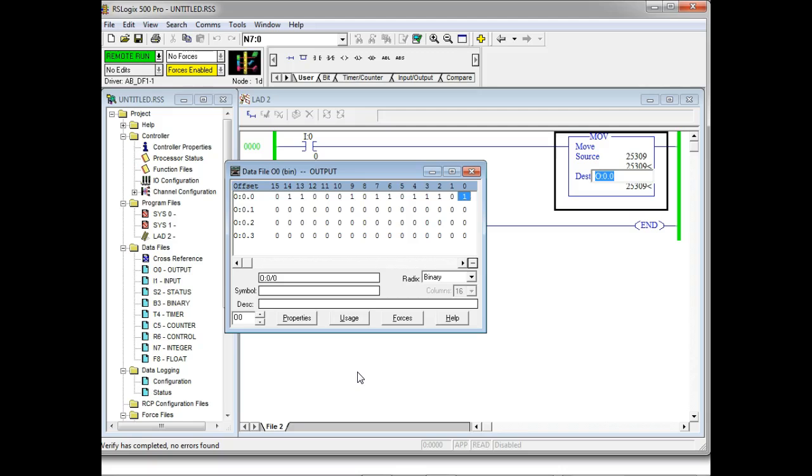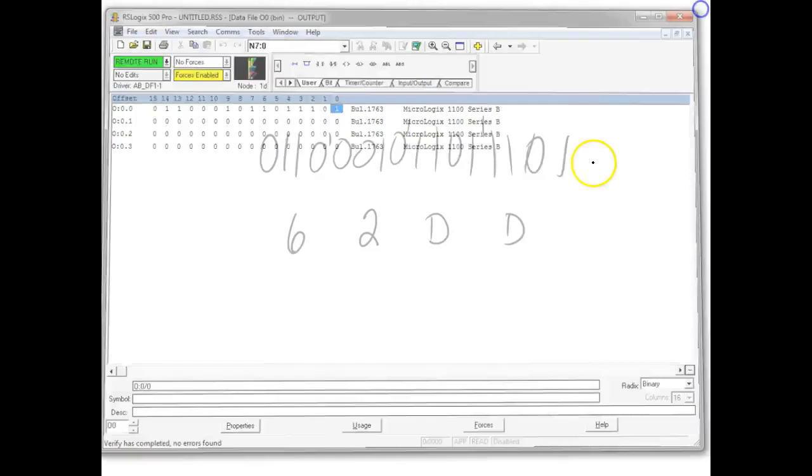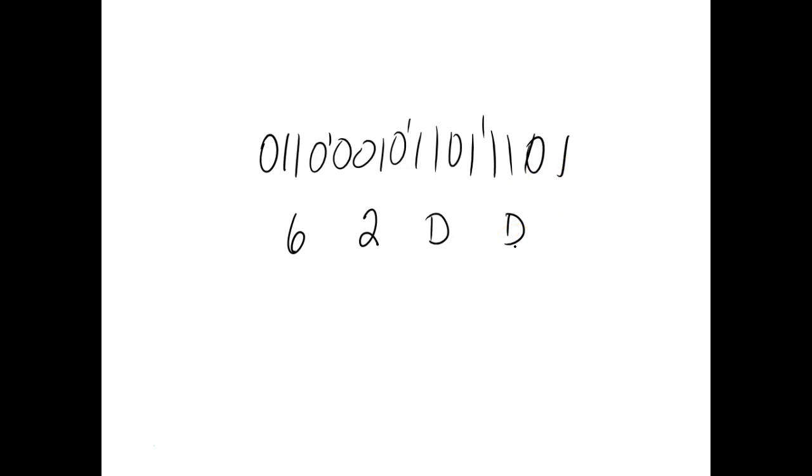So that's where these bases come into play, especially when we're dealing with getting information and sending it to an output port directly without using output to energize instructions. So you can set up those output ports any way you want to, right? You understand, and good gracious guys, that would save tons of code. Instead of me turning on a lot of relays or turning on a lot of outputs just to get the outputs in a certain state, right? You understand? What could you do? You could set them in that state with a what? With a move instruction. One move instruction. Cool, right? Very powerful. The move instruction.